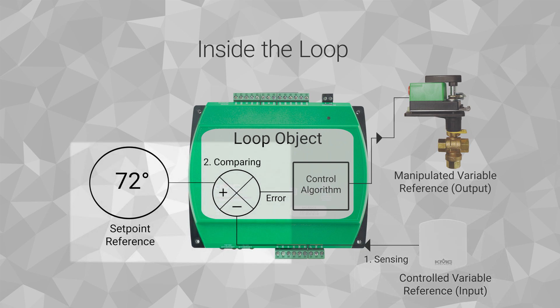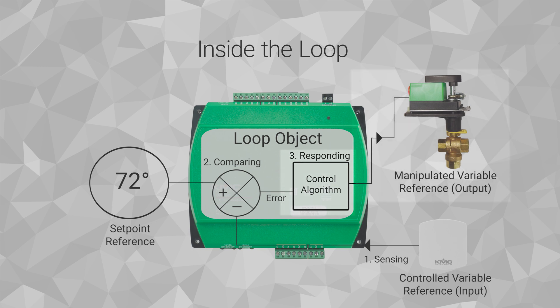Next, we compare the measurement of the current condition to the desired set point. The set point may be a fixed value maintained in either a loop object or value object, or from a user input device such as a thermostat. The control algorithm then responds within the loop object by reacting to any error that may exist by generating a corrective control signal.